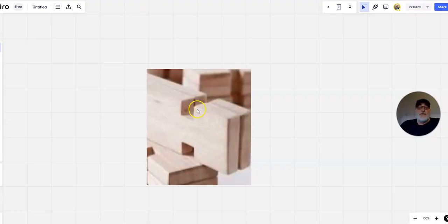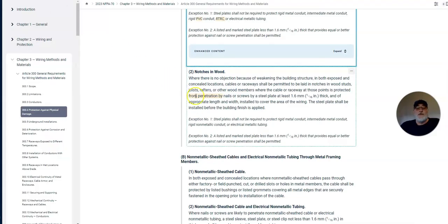This is an example of a notch in the wood. Basically, you're just taking a little chunk out of the wood, but not cutting so much of it out that you're structurally compromising the wood itself. That's what they're talking about when you go back and look at the NFPA, the notches in wood, where there is no objection because of weakening the building structure. In both exposed and concealed locations, cables and raceways shall be permitted to lay in notches in the wood studs, joists, rafters, or other wood members where the cable or raceway at those points is protected from penetration by nails or screws by a steel plate at least 1/16 inch thick, of appropriate length and width, installed to cover the area of the wiring.